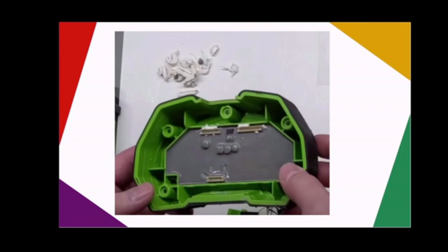And all you have to do is take these lids off from each end. There may be a few screws on the bottom. There look to be about 5 here for each of the side lids. So remove those. Once you remove those, you're going to see 3 small connectors with sealant. Remove the sealant gently and then remove the connectors. Pull them out. Make sure that you're gentle and you pull on the connector itself, not the wiring. You don't want to pull any wire out of the connector. No need to remove anything else other than the white sealant.